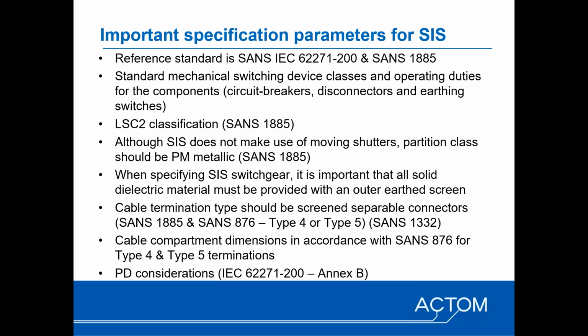And it's maybe worth noting that in 62271-200, where it covers PD testing, values for PD have not been prescribed, mainly due to the complexity and the fact that different switchgear assemblies incorporate different technologies ranging from gas to oil to air to solid dielectric. So it's very difficult to prescribe values. It is recommended, and it's in a note, that for solid dielectric switchgear PD less than 20 picocoulombs would be appropriate, which we agree with. In our case, we're even more conservative, and we ensure that the switchgear complies with a maximum of 10 picocoulombs, so less than or equal to 10 picocoulombs.